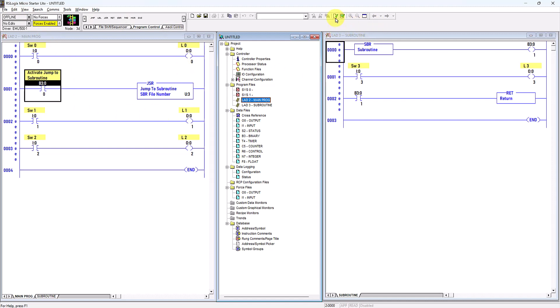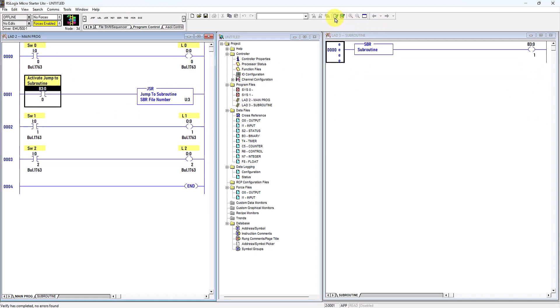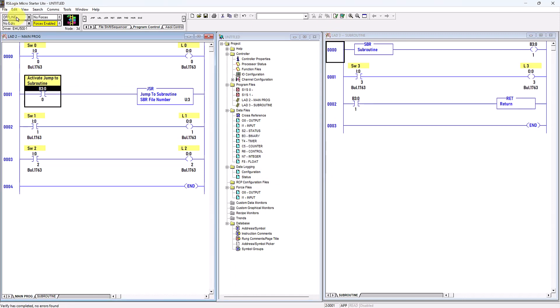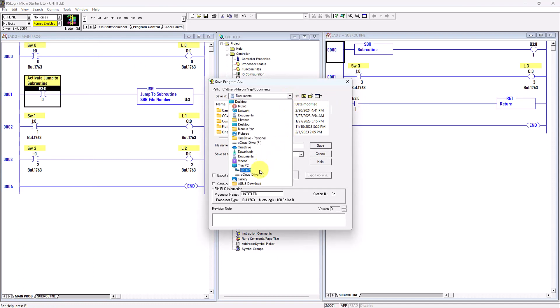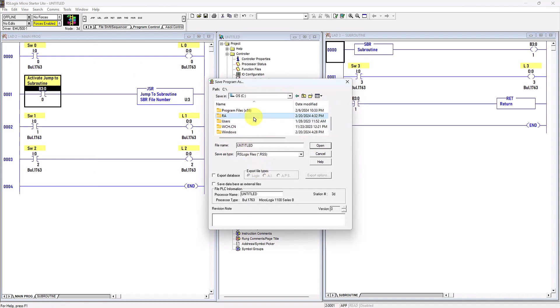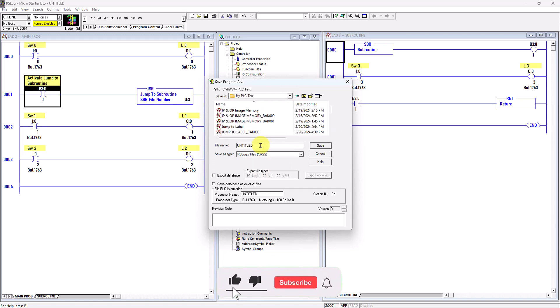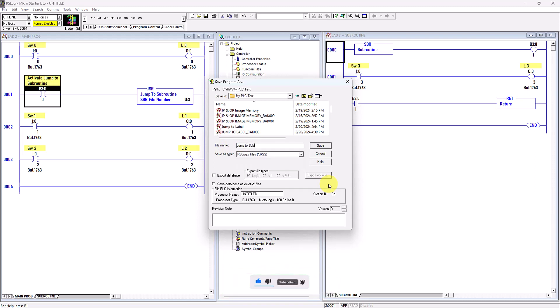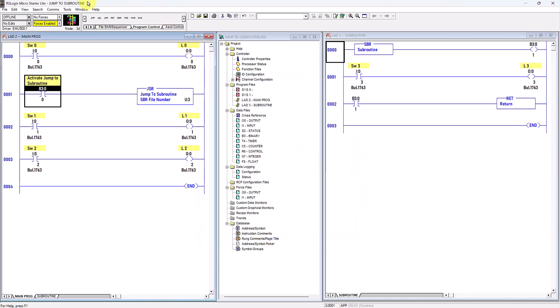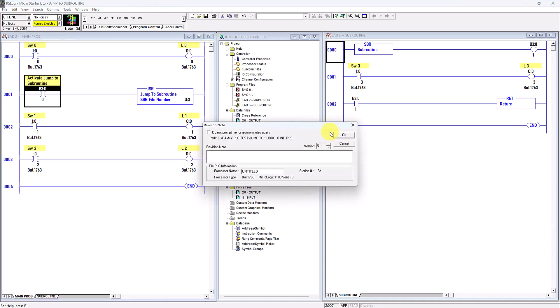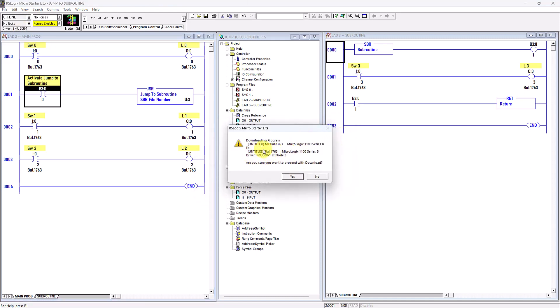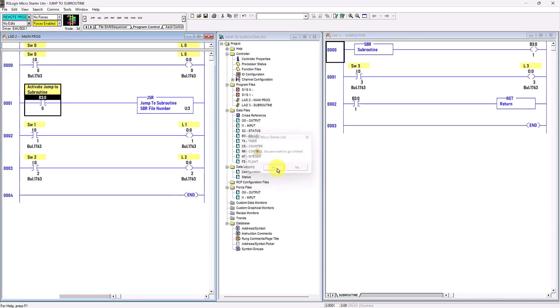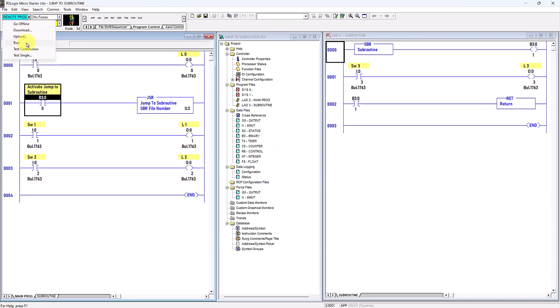Let me verify the file to make sure there are no errors — click Verify File, then Verify Project. No errors. Then save the file to the computer hard disk, give it a name such as 'Jump to Subroutine', and click Save. Then click the down arrow key, click Download to our virtual PLC — Emulate 500 — click OK, then select Run.